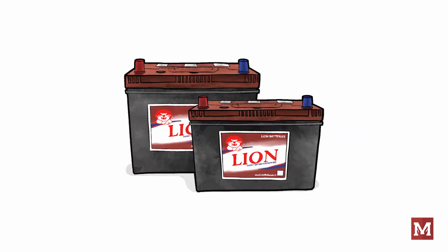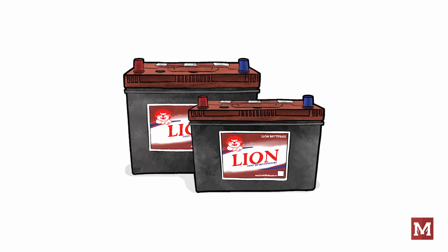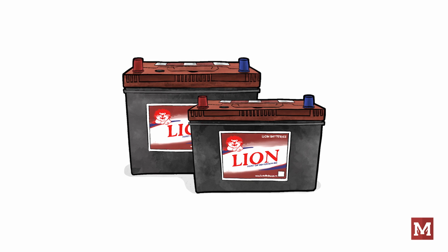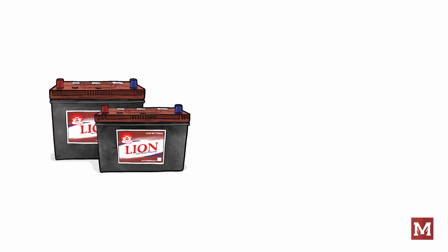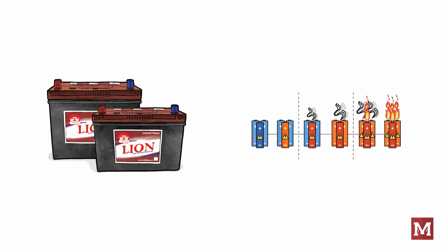So, then we have lithium ion, which has dominated the ESS market as of late, mainly due to its high energy density, small footprint, and efficiency. They also have about a 20-year lifespan and have fast charge and discharge times. However, they are more sensitive to extreme temperatures and are more volatile.